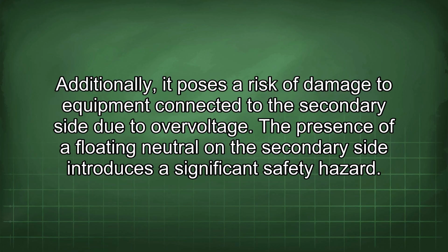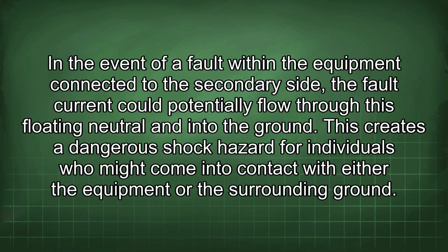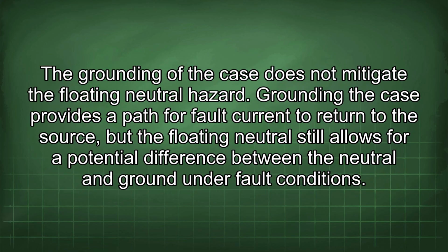The presence of a floating neutral on the secondary side introduces a significant safety hazard. In the event of a fault within the equipment connected to the secondary side, the fault current could potentially flow through this floating neutral and into the ground. This creates a dangerous shock hazard for individuals who might come into contact with either the equipment or the surrounding ground. The grounding of the case does not mitigate the floating neutral hazard.